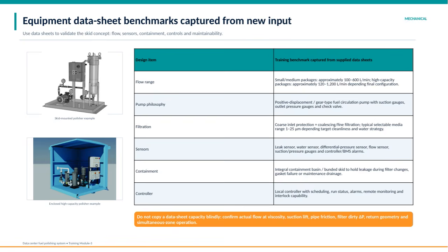Containment is designed to prevent leaks, featuring an integral basin or bund skid to catch any spills during maintenance or filter changeouts. The controller itself is local but quite advanced, providing scheduling, run status updates, alarm notifications, remote monitoring, and interlock capabilities to maintain safety and efficiency.